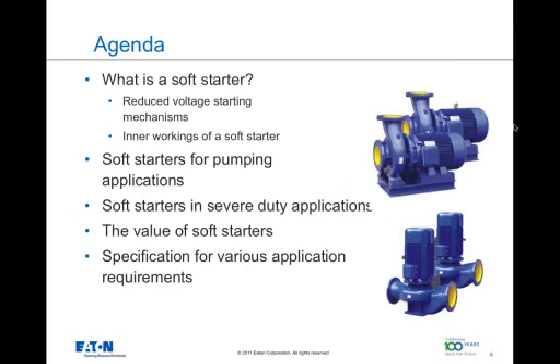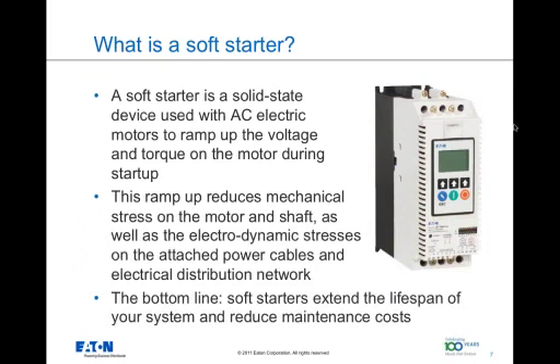I got to preface by saying that every motor out there deserves a soft starter. And now, what is a soft starter? A soft starter is a solid state device which gradually ramps up the voltage and hence the torque associated with it. As a result of the gradual ramp up of the voltage, and the torque associated with it, the mechanical and the electrodynamic stresses that are generated in the system are greatly reduced. And because of this reduction in the stresses in the system, life increases and your maintenance cost decreases. So that is the biggest value prop of using a soft starter. Your system life increases and your maintenance costs go down quite a bit.